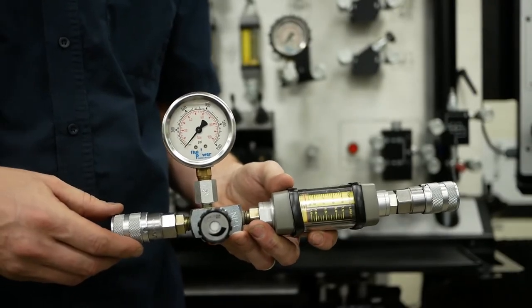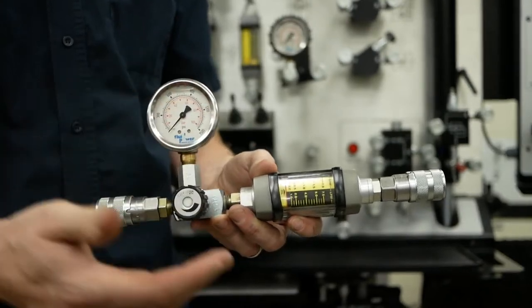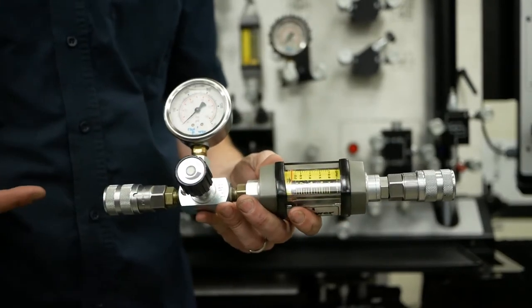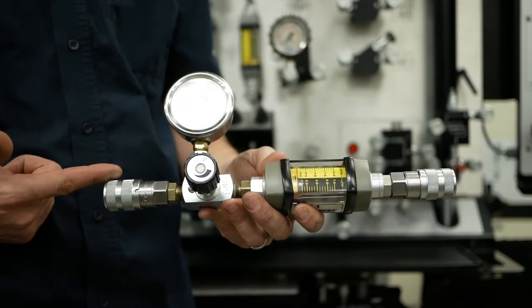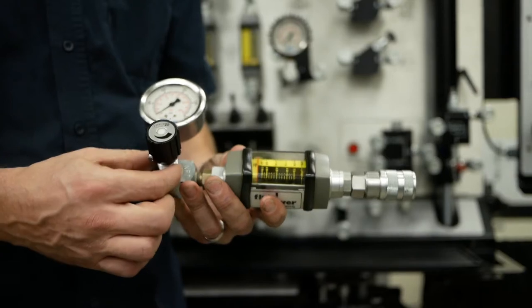A bypass test we use to check the pump's flow rate. To do that, we're going to use this flow meter right here. We hook up from the pump into this side connector here, and we open up this needle valve or this restrictor flow control right here.